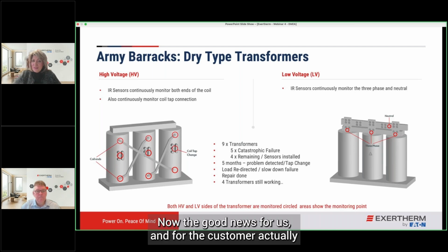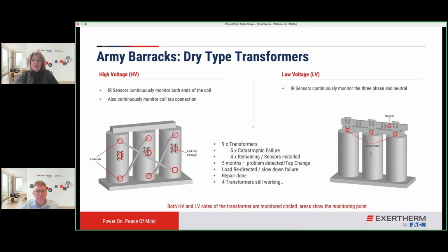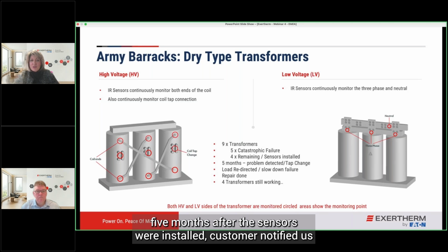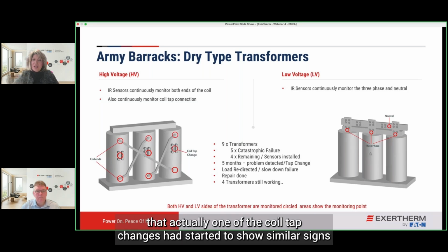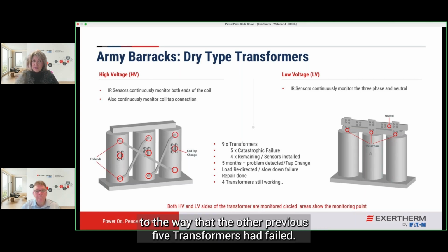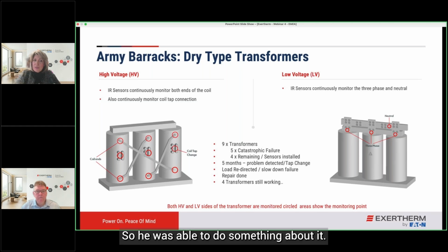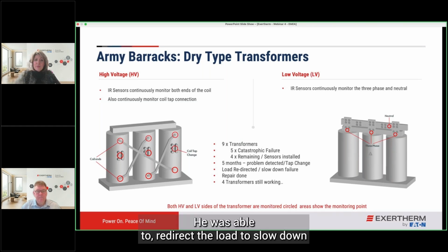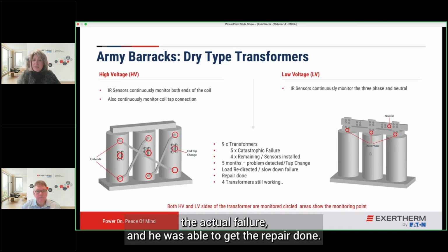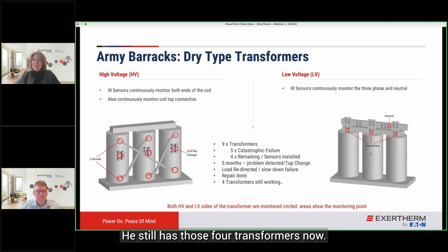Now, the good news for us and for the customer, 5 months after the sensors were installed, the customer notified us that one of the coil tap changes had started to show similar signs to the way that the previous 5 transformers had failed. So he was able to do something about it. He was able to redirect the load to slow down the actual failure, and he was able to get the repair done. He still has those 4 transformers now. So we had 9 sensors on the HV and 4 on the LV side.